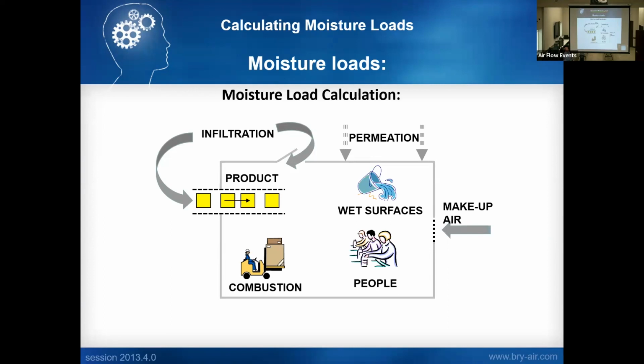The product could be several different areas of load. You could have a conveyor going through the space, bringing product into the space. That opening for the conveyor is going to have moisture infiltration. And if you're drying the product in the space, you're going to have the moisture you're removing from the product added to the space as well. And sometimes you also have process. If a customer's doing a wash down cycle, washing down a pharmaceutical or something, and they need to dry that space out to start another production run, you also have wash down to deal with.